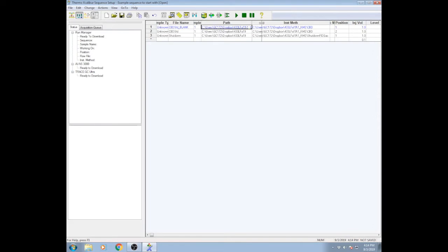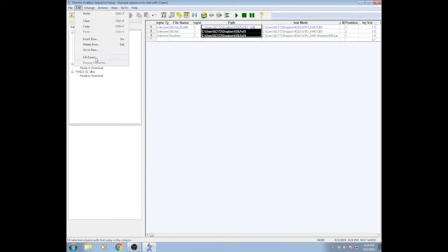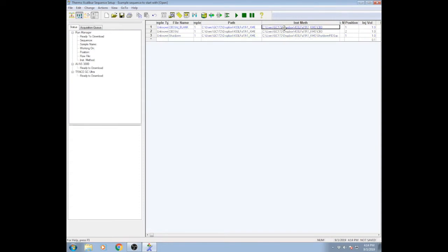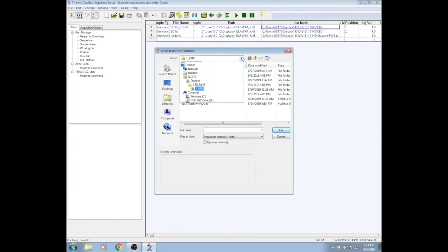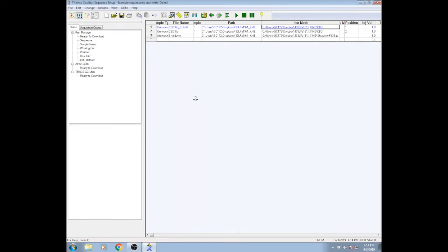One nice thing with the software is if you've done something on the top row and you have a bunch of rows, you can highlight those rows and go to Edit, Fill Down, and hit OK, and it'll do all that for you. So the instrument method, you can start off with the CBD, you can use the method that I gave you. And when you develop new methods, start from an example method. And that's how the instrument actually runs that. We'll cover that in a subsequent video.